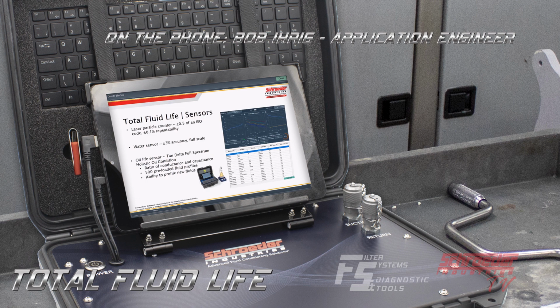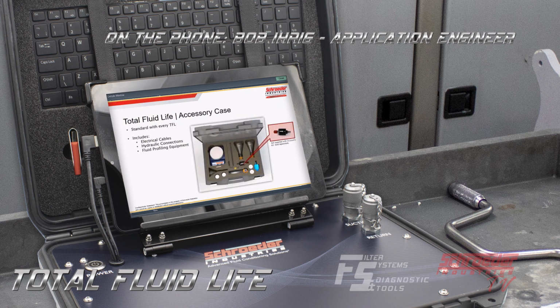With this unit, it comes preloaded with 500 fluid profiles, many of the main fluids that we see out in the field today. It also has diesel fuel in it and some other interesting fluids as well. But we've already run into cases where it's necessary to profile custom fluids or new fluid profiles into the system. And with this unit, you have the ability to do that, create custom fluid profiles. And that involves some of the accessories, such as the hot plate and the flask that we include in our standard accessory case, which also includes the electrical cables and hydraulic connections.